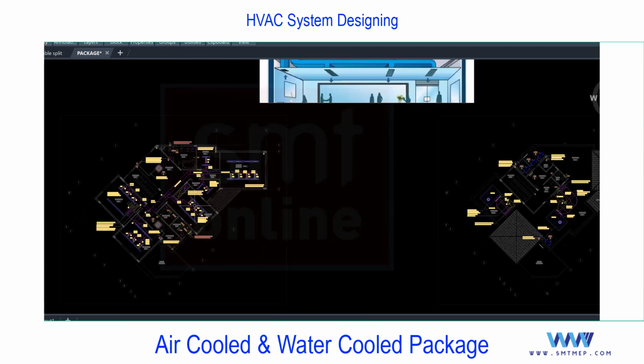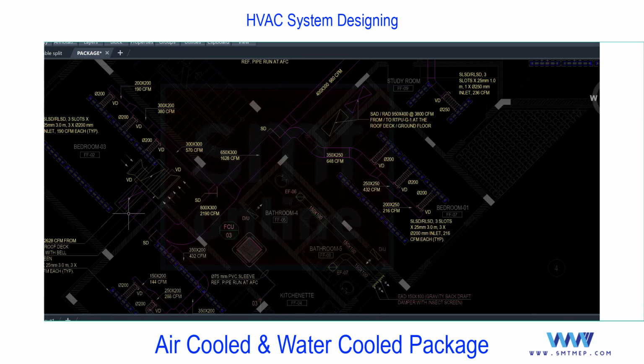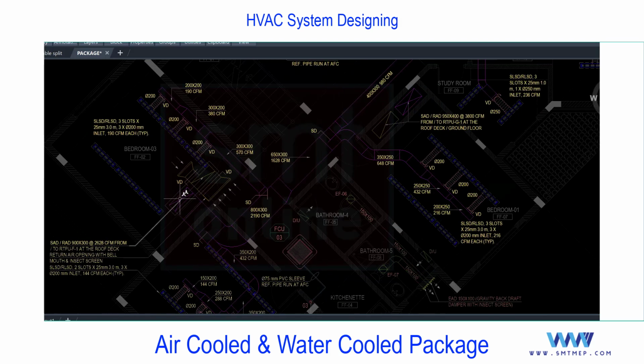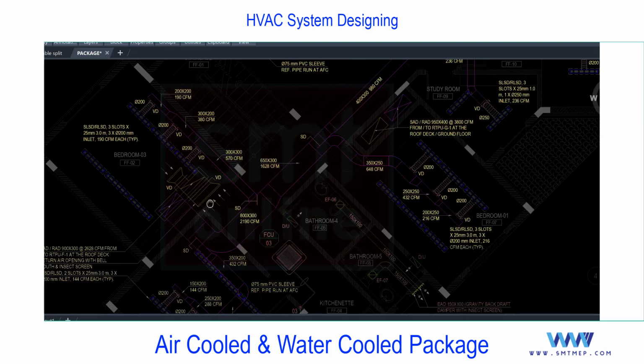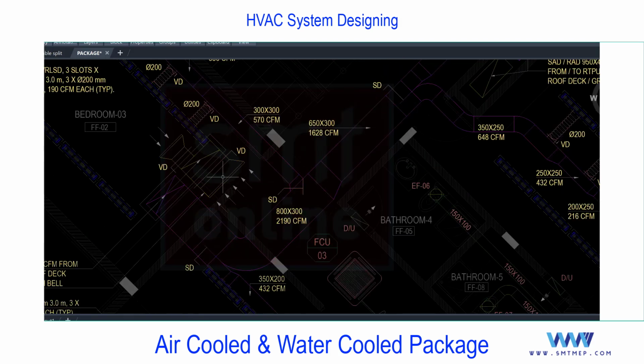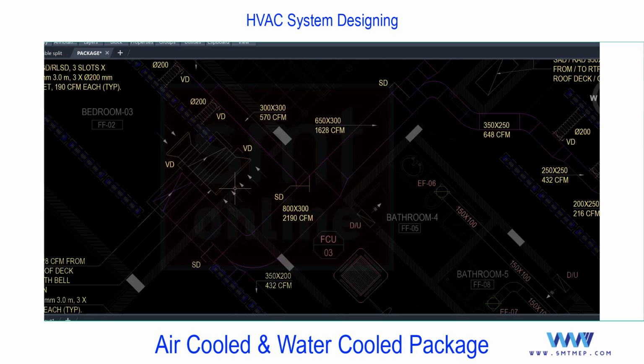This left side is the first floor. You can find, you see, this duct is entering the first floor after the vertical duct and supplying the air to the complete first floor. And if you talk about return, you see, return is only a piece of duct. This is called bell mouth. We are not running the return like supply, because above the false ceiling the complete area we can consider as a single zone.